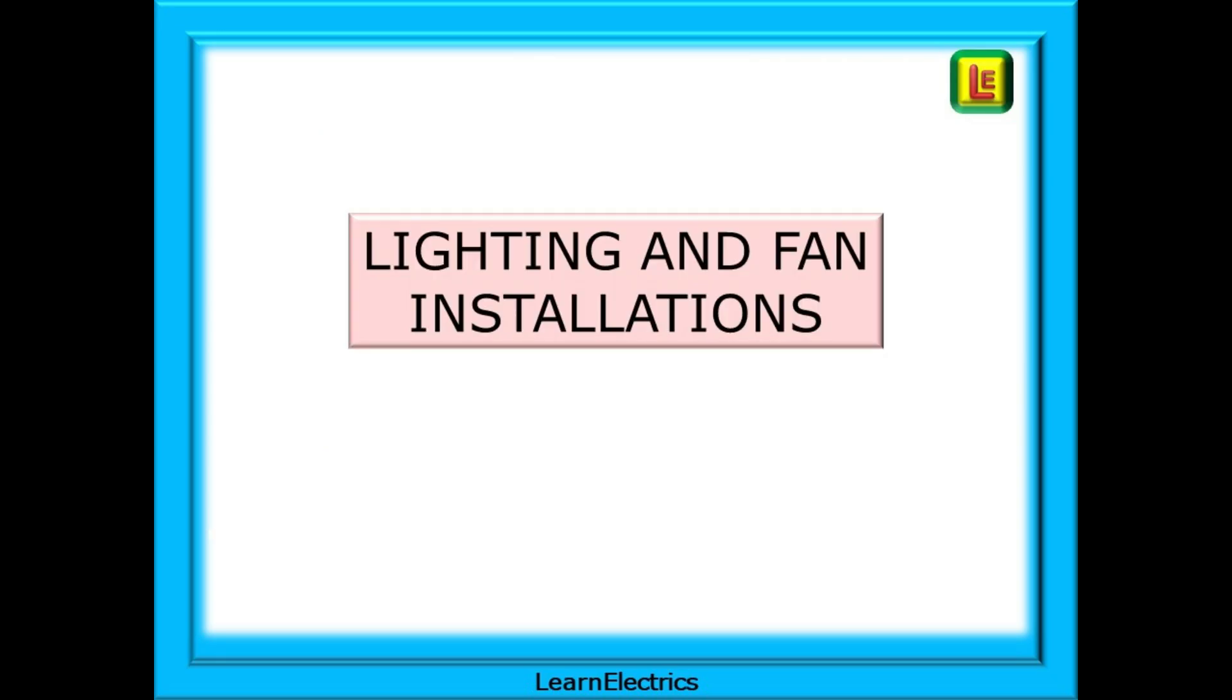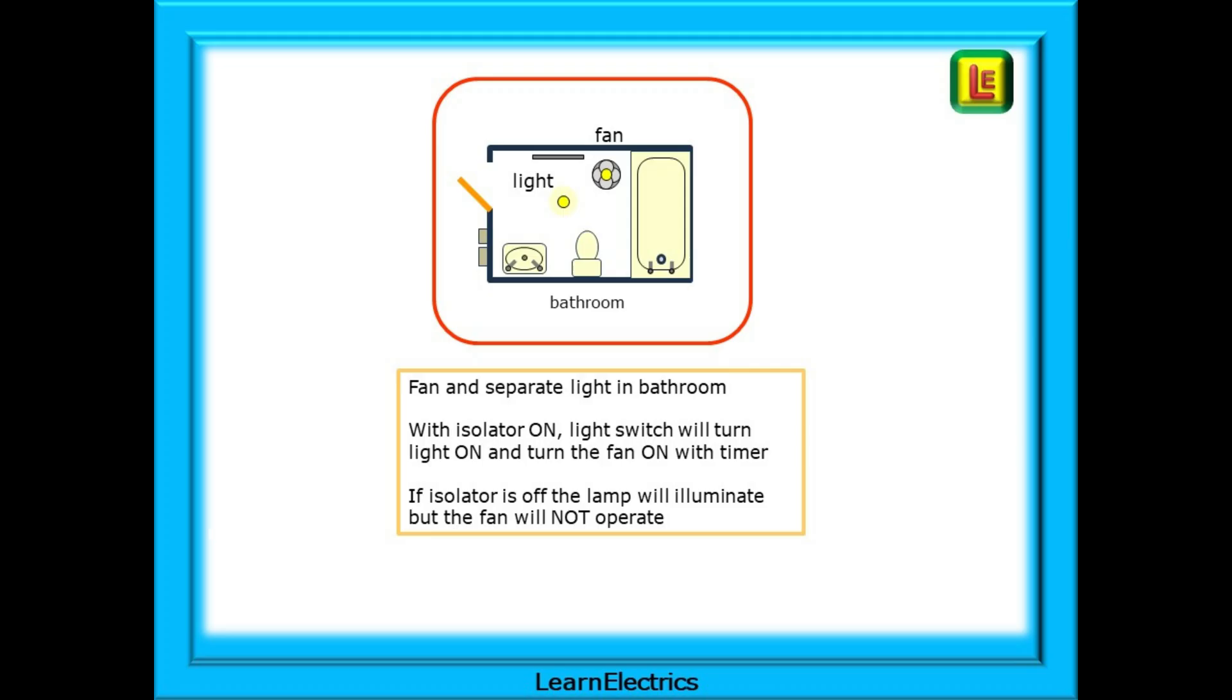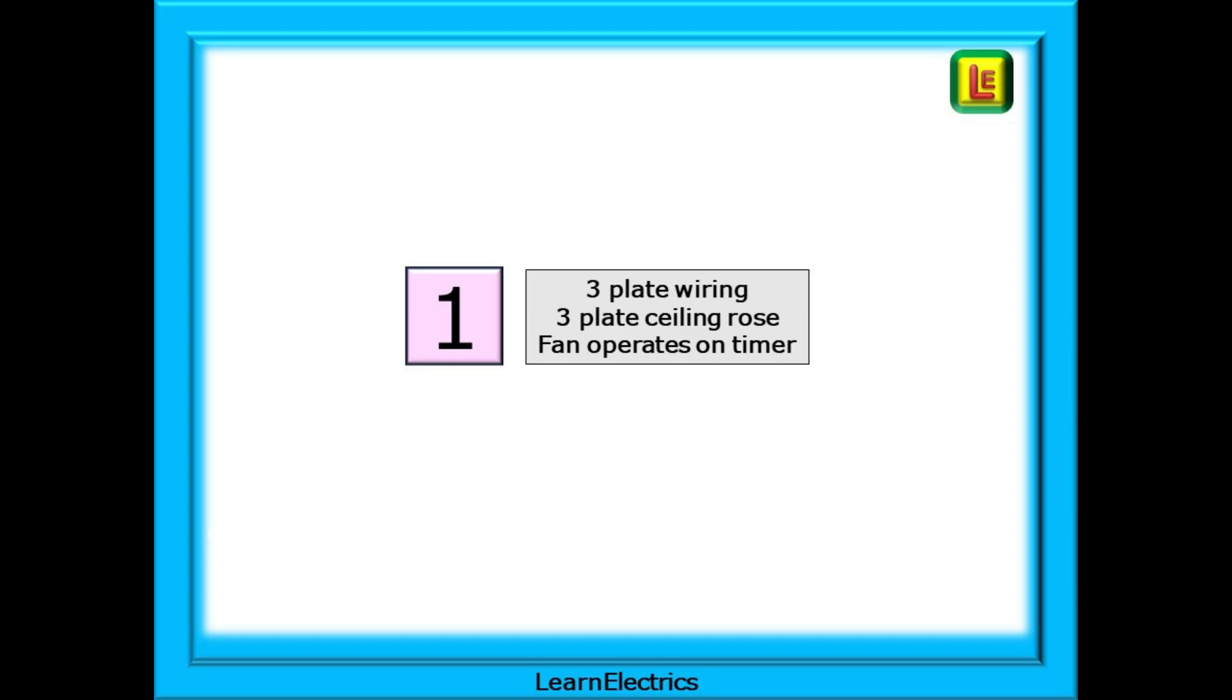Let's look now at some lighting and fan installations. This is the basic layout of a fan with a separate light in a bathroom. With the isolator on the light switch will turn the light on and turn the fan on and enable the timer function. If the light is turned off the fan will continue to overrun for say 10 minutes. If the isolator is in the off position the lamp will illuminate but the fan will not operate.